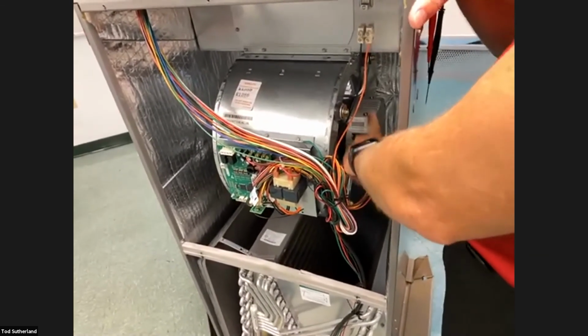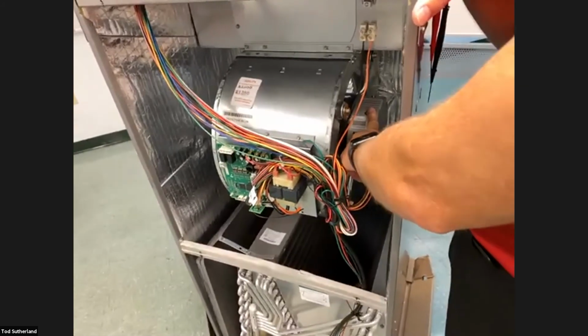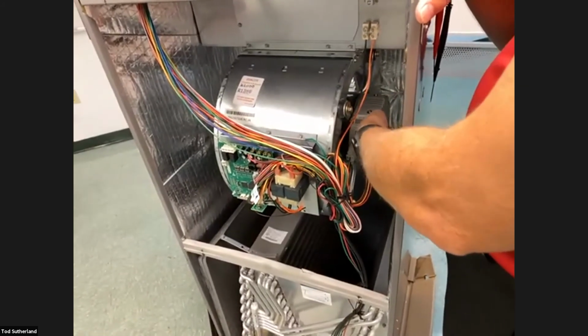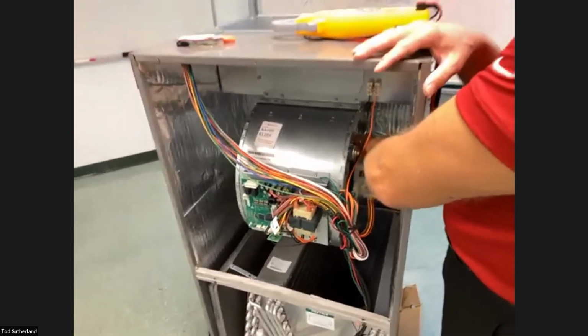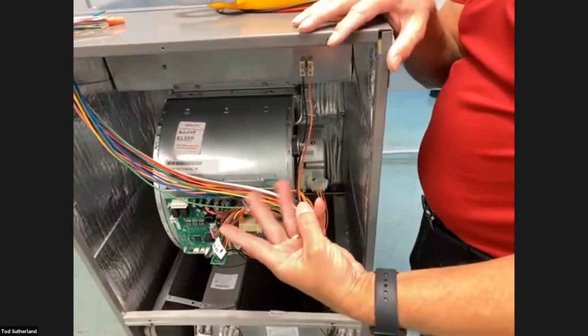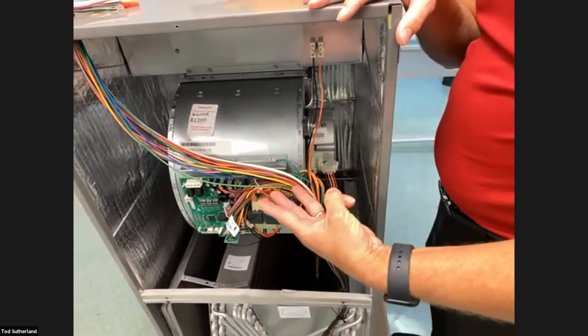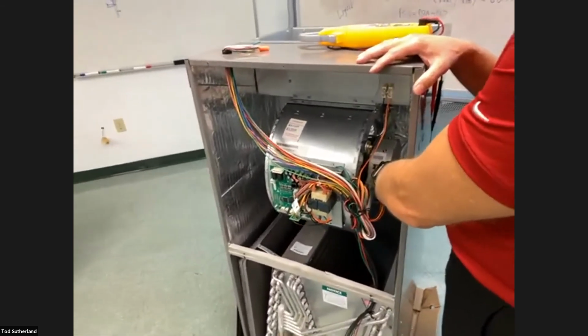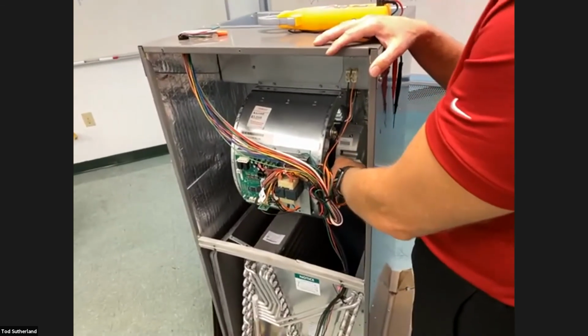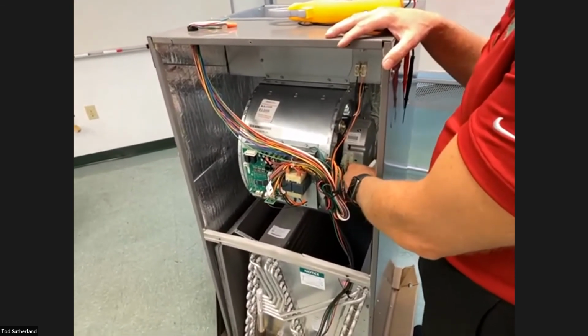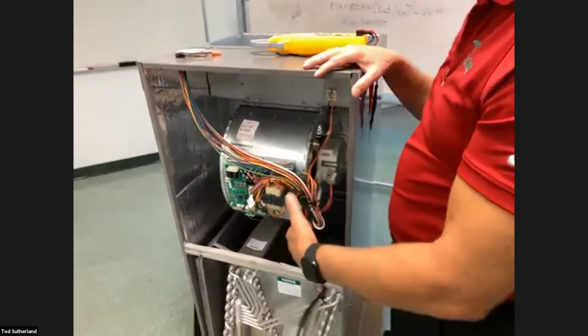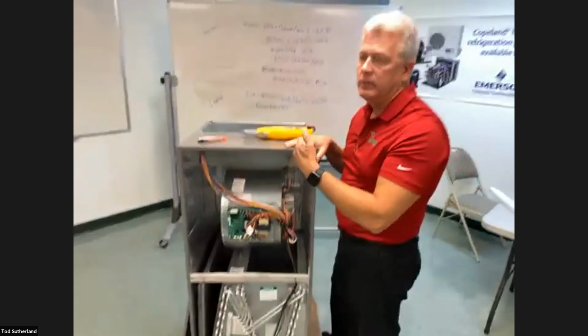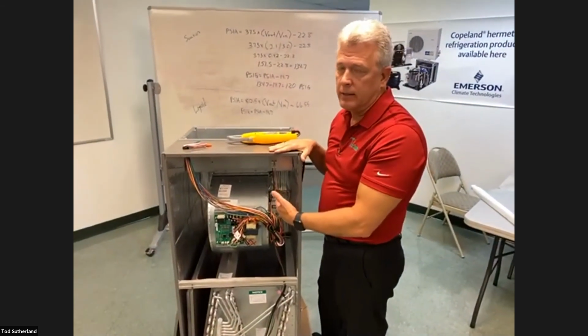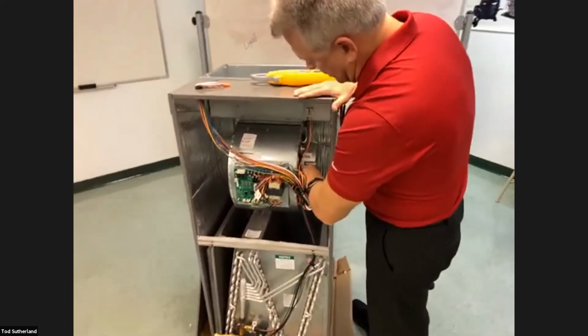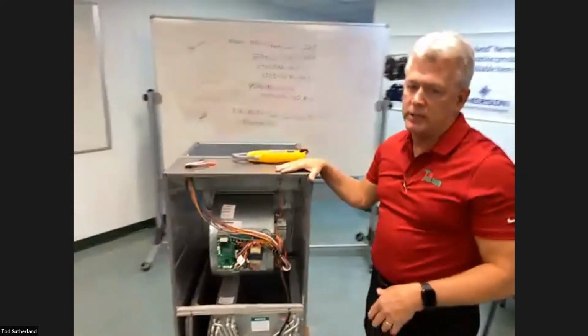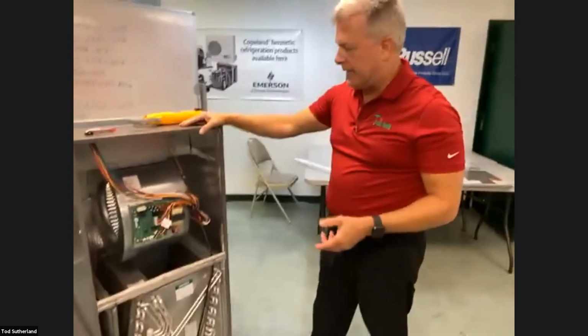And then just like any other variable speed fan motor, you can remove the end bell, disconnect the wiring between the module and the motor, which is 3 wires. You're going to ohm each wire to itself, and they should all read the same. And then you're going to ohm each wire to ground for resistance, and they should all be open. If any of them are less than 100,000 ohms, I believe it is, then you've got a shorted motor. Okay, that's standard procedure on any variable speed motor. Not specific to this air handler. It's in your Genteq books that you can find any information on that.